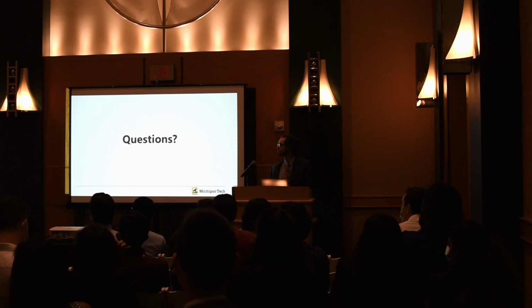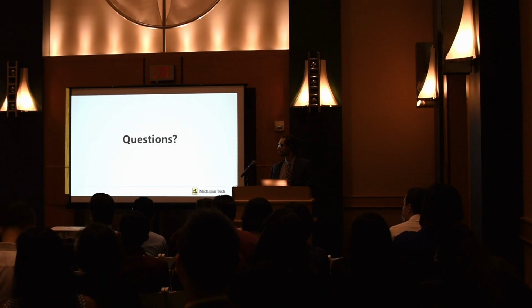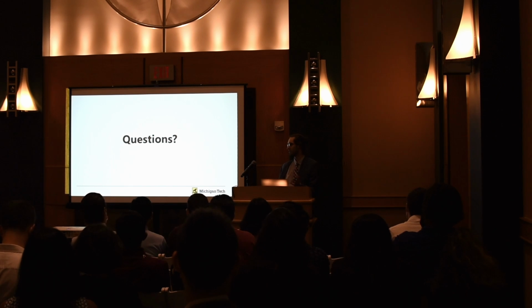So that's the transient valve, right? And your time for failure, or is it time? So the reason we're using a statistical model here instead of something like AI or any more complex tools is that we see variations between each cardiac cycle, right? So if cycle 1 is 18 millimeters of mercury, cycle 2 isn't always going to be 18 millimeters of mercury.